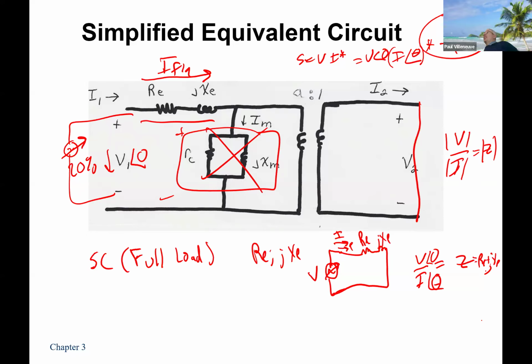They're the same. It all gets lumped together, right? So they get lumped inclusively. It's actually a very practical experience. So this short circuit over here is going to be, let's say, 2000 amps. And I run a very short wire between the bushings, right, to make it 2000 amps. Over here, maybe I need 200 amps. But now I've got a whole test rig set up where I've got to run cables and all that stuff. So is it easier to get wires that are running at 200 amps or 2000 amps?